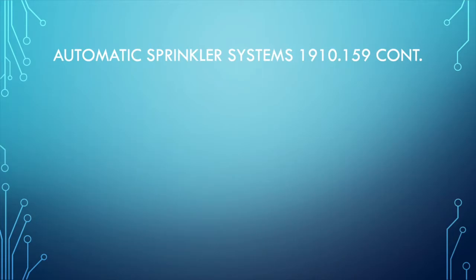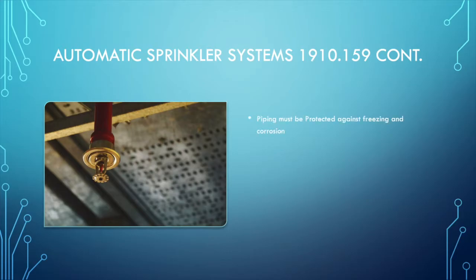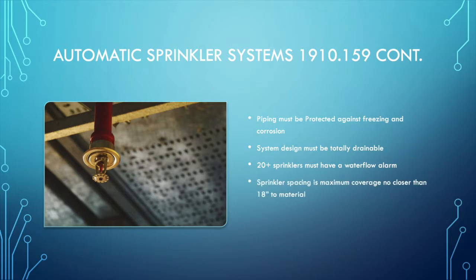Automatic sprinkler systems, 1910.159, continued. Piping must be protected against freezing and corrosion. System design must be totally drainable. 20 plus sprinklers must have a water flow alarm. Sprinkler spacing is maximum coverage, no less than 18 inches to material. Identifiable by location, number, and basis of design.